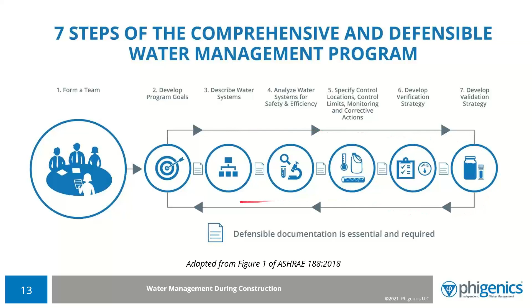In terms of construction, there are lots of aspects to 188, but today we're focusing on construction activities. The building owner is required under section 4.2 to survey the existing building—this is how you opt into the standard. But a lot of people don't read the rest of that paragraph, which is what people do for their ongoing operations. However, you also need to do this if you have a new building emerging, or renovations, additions, or modifications to the existing building and its water system, because any of those activities could upset the balance of that water system.